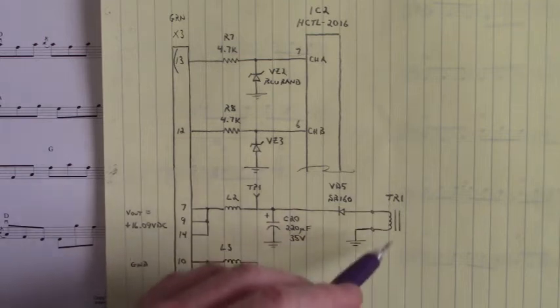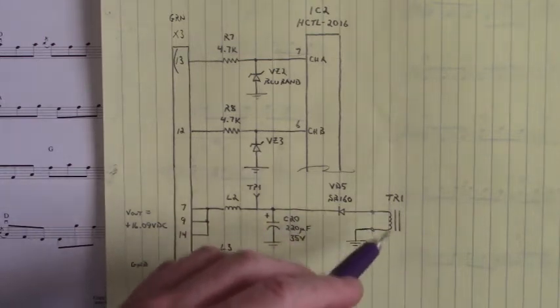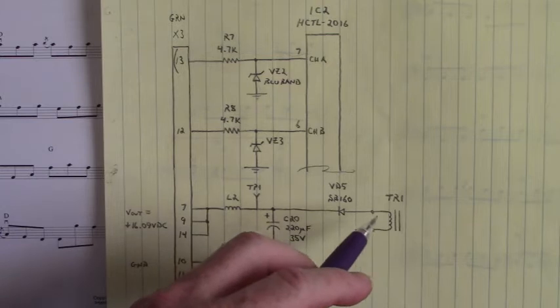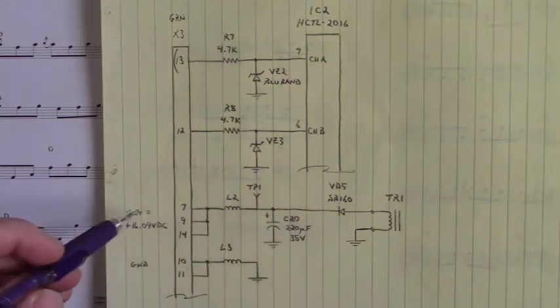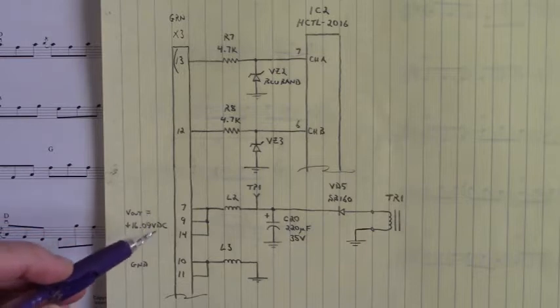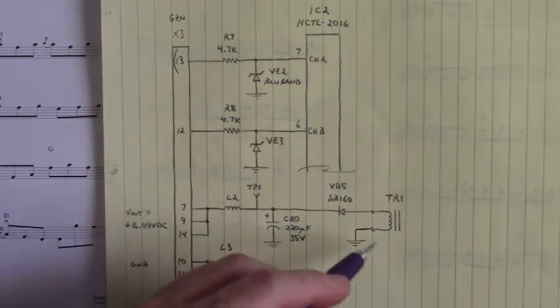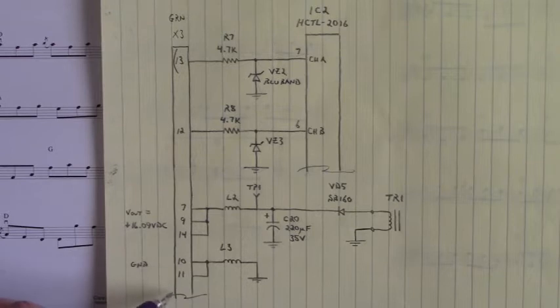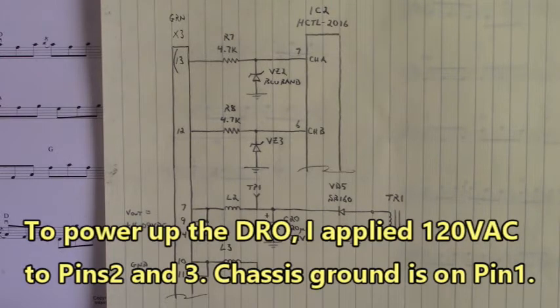Now we have this secondary from the switch mode power supply that creates a DC voltage and applies it to pin 7, 9, and 14 with ground on 10 and 11 of that Phoenix connector. I applied 120 volts AC single phase to pins 2 and 3 of that Phoenix connector, and pin 1 being earth ground, frame ground back to earth.